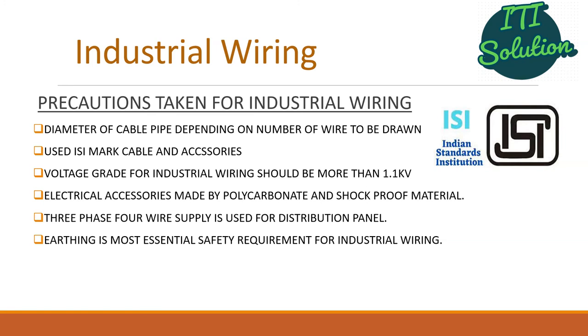Now let us learn the precautions taken for industrial wiring. Number one: diameter of cable pipe depends on number of wires to be drawn. Number two: use ISI — Indian Standards Institution — marked cable and accessories. Voltage grade for industrial wiring should be more than 1.1 kV. Electrical accessories should be made by polycarbonate and shockproof material. Three-phase four-wire supply is used for distribution panel. Earthing is the most essential safety requirement for industrial wiring.